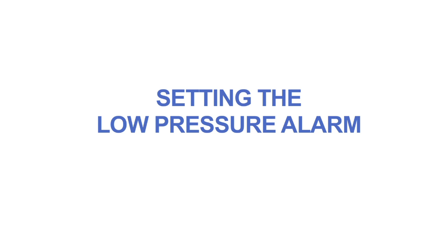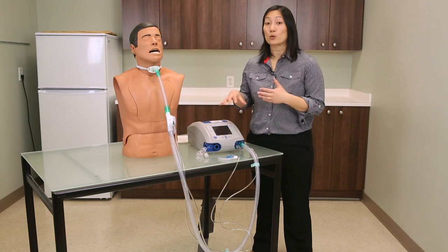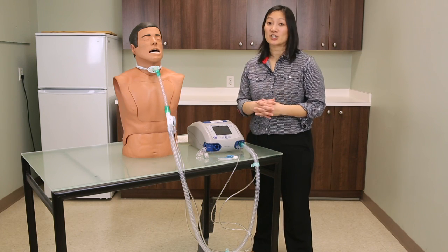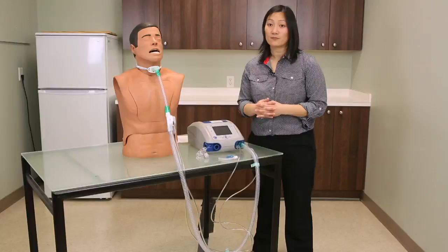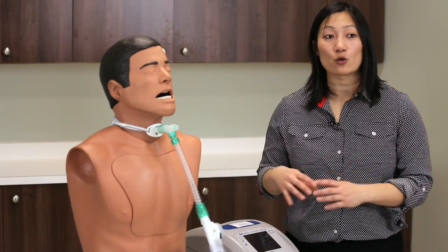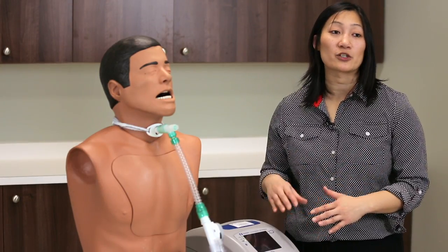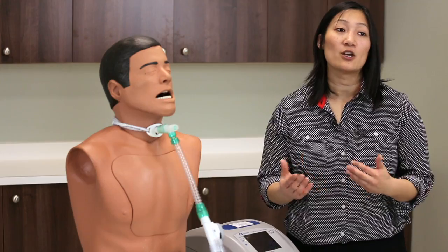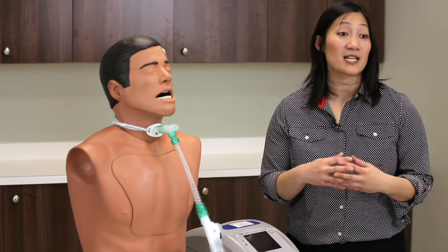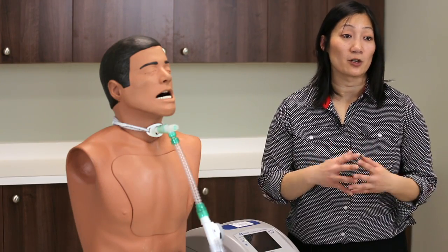So how do you set the low pressure alarm so that the ventilator will actually alarm when the client is disconnected? First, you want to take into account the normal ventilatory pressures of the client so that you can use these as a reference when you set the low pressure alarm.